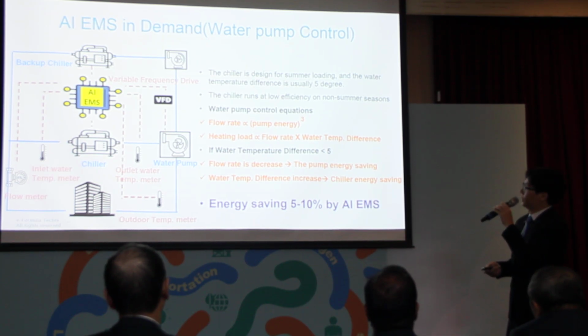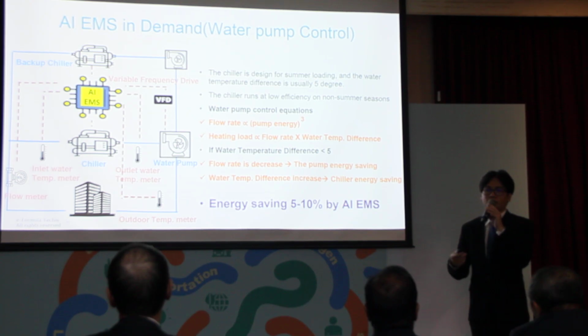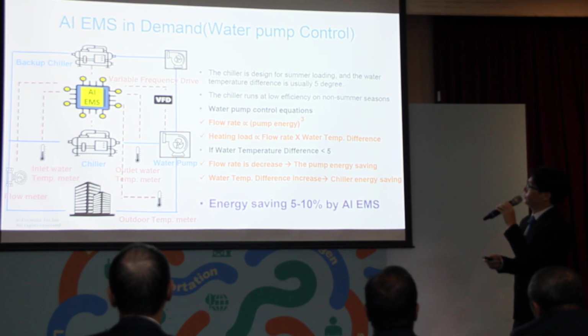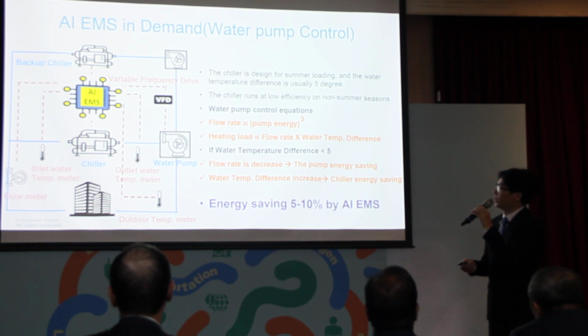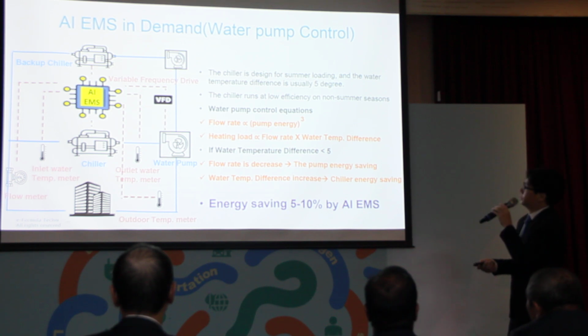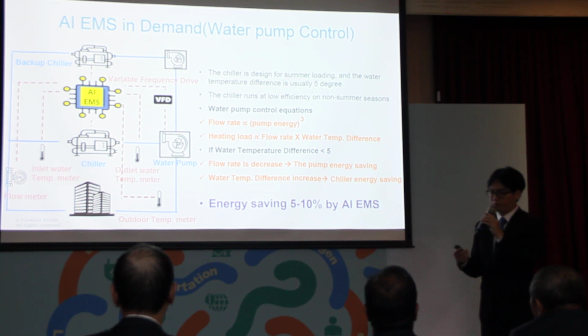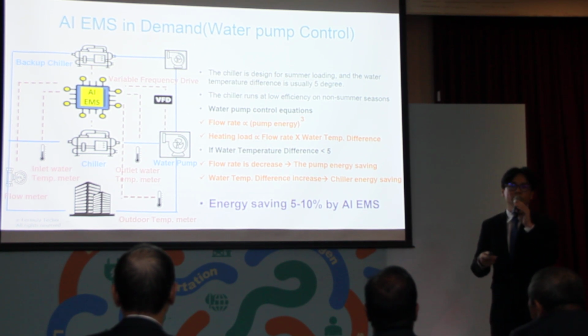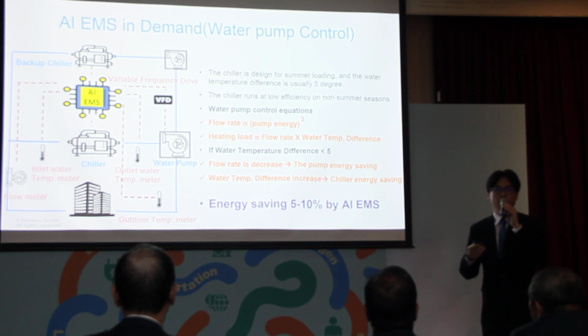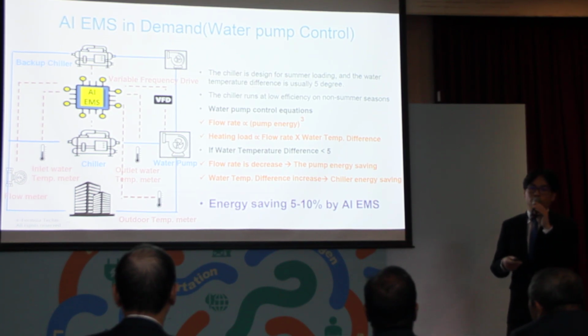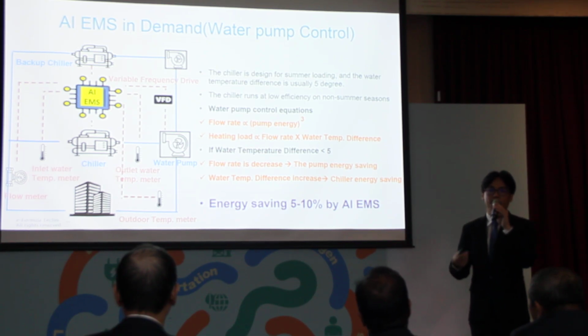So we can put the flow meter and the temperature meter between the inlet and outlet of the chiller, and we can use the VFD, variable frequency drive, to control the pump to perform a control loop. Okay, so if we find the water temperature difference is below 5 degrees, it means that we can decrease the pumping flow rate. So from equation 1, we can get a very high energy saving from the pumping result.